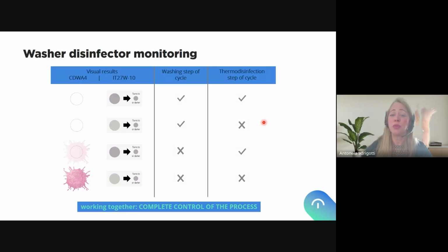In this one, the second row, we have a successful washing step, but something happened with the time or the temperature in that location where the indicator was positioned that is not making me able to guarantee the right level of disinfection I was expecting. Meaning I cannot guarantee the right level of disinfection of the instruments in that location. And this is why it's so important, because inside the washing machine, the sensors are not located where the load is. They are located in specific parts of the washer machine, but we have to make sure that the right temperature reaches the instruments. And this is why we need this type of indicators, as well as the washing indicators.